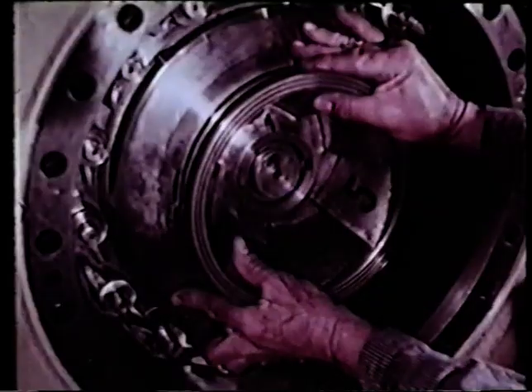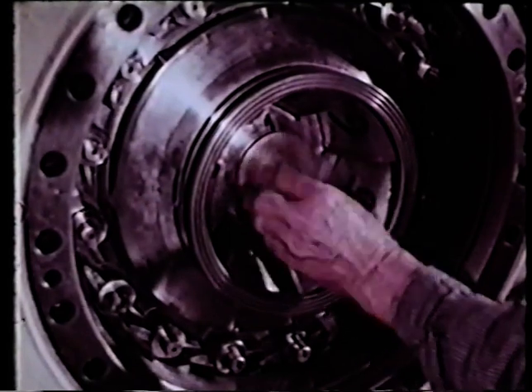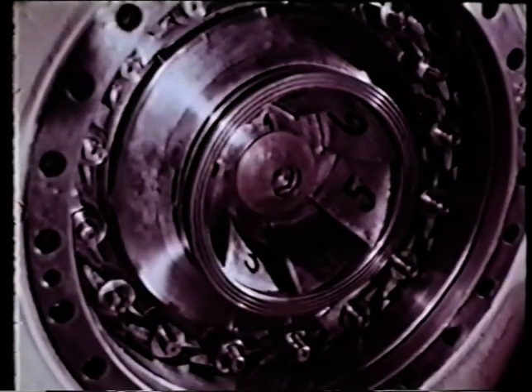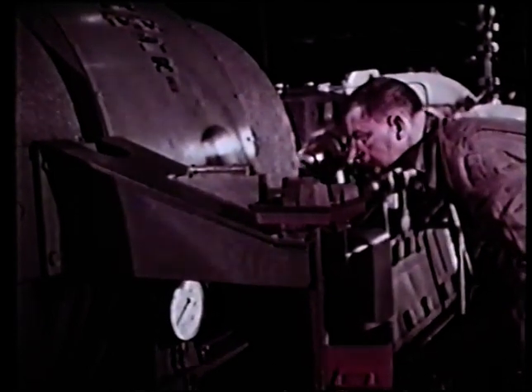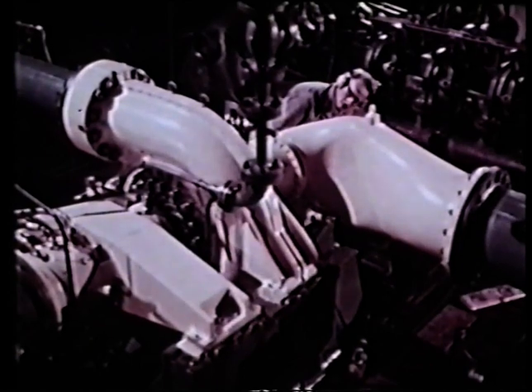High-power full-head models were used in the cavitation test program to confirm the indications of low-head measurements. Suppression of the damaging cavitation bubbles, more exacting with a pump than with a turbine, needed a Thoma number of 0.15, corresponding to a runner mounted 150 feet below the level of the loch. This is deep, but with an underground station, not expensive to provide.